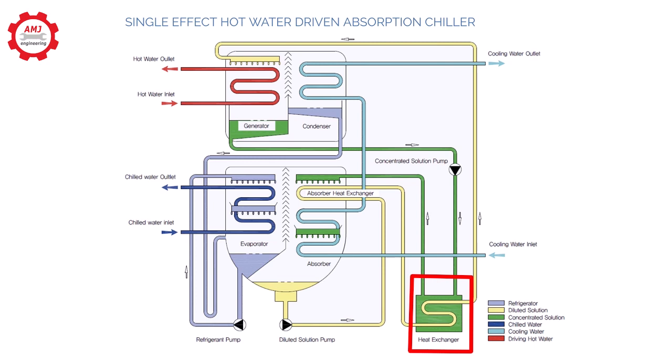Heat exchanger: The heat exchanger transfers heat from the relatively warm concentrated solution being returned from the generator to the absorber and the dilute solution being transferred back to the generator. Transferring heat between the solutions reduces the amount of heat that has to be added in the generator and reduces the amount of heat that has to be rejected from the absorber.